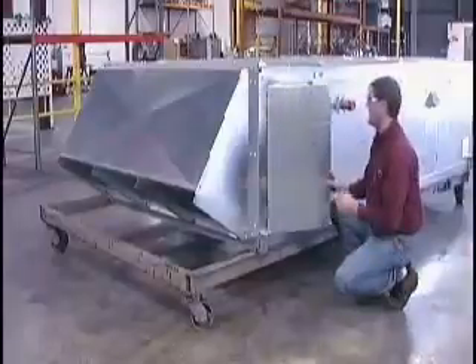Before the preheat coil, we usually put the filters. Now, the filter is a very, very important part of the unit because we're trying to filter the bad stuff from the outside to keep it from coming in. It could be chemicals in an industrial location like this. It could be particulate. We can filter out solvents and chemicals with chemical filters. So you can, and again, we're only buying a unit for ventilation air so we can afford to put in the right kind of filtration.